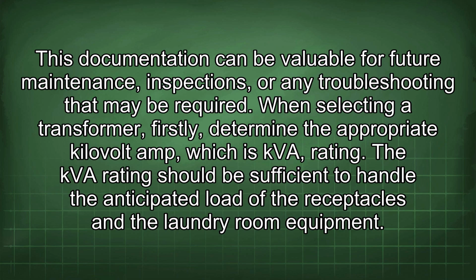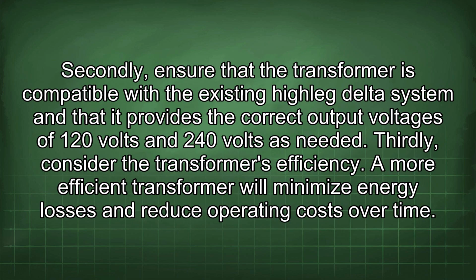When selecting a transformer, firstly determine the appropriate kilovolt-amp, or kVA, rating. The kVA rating should be sufficient to handle the anticipated load of the receptacles and the laundry room equipment. Secondly, ensure that the transformer is compatible with the existing Highleg delta system and that it provides the correct output voltages of 120 volts and 240 volts as needed. Thirdly, consider the transformer's efficiency. A more efficient transformer will minimize energy losses and reduce operating costs over time.